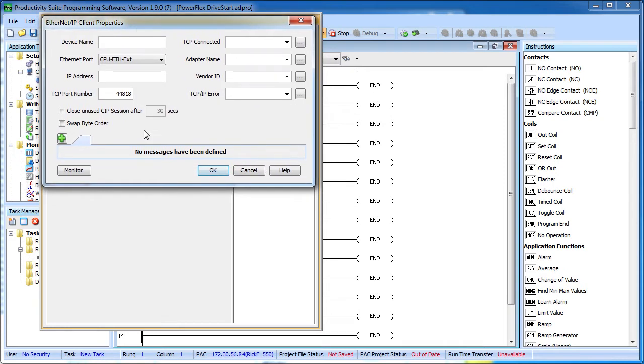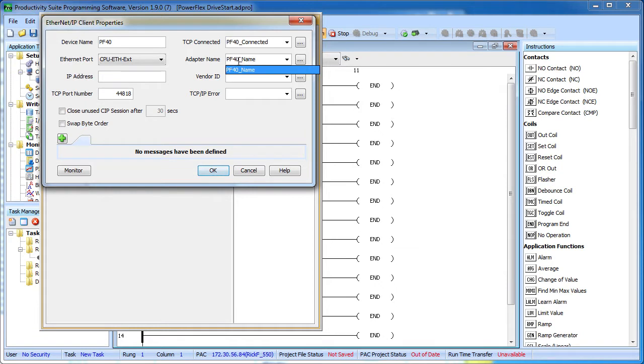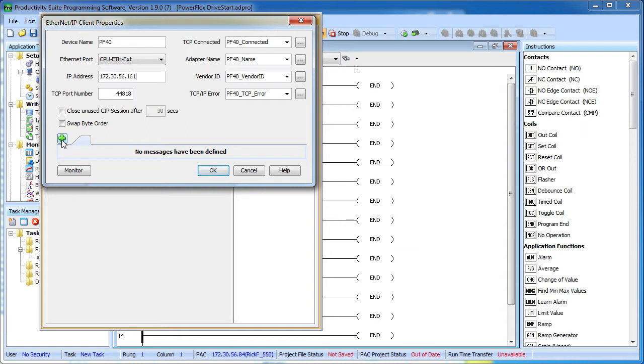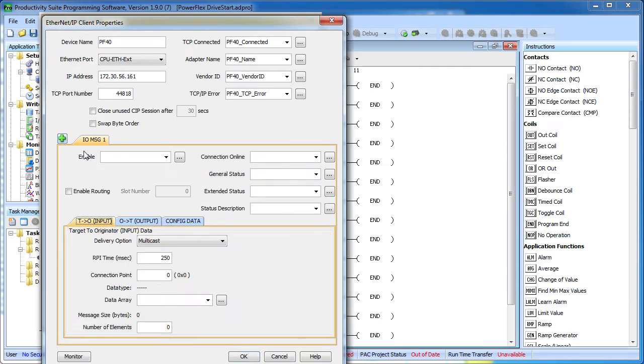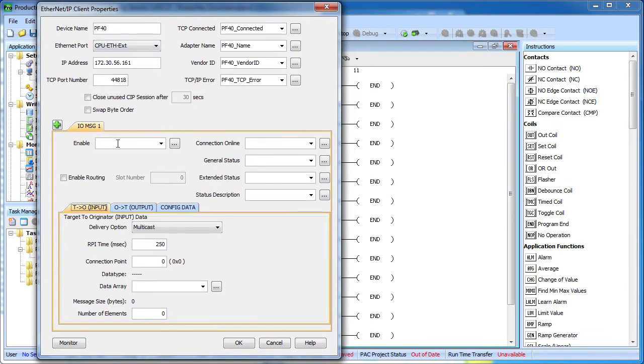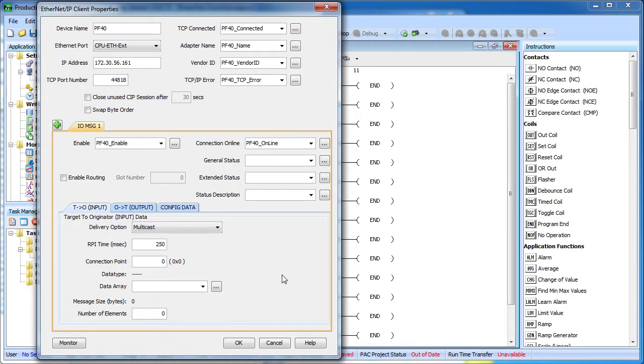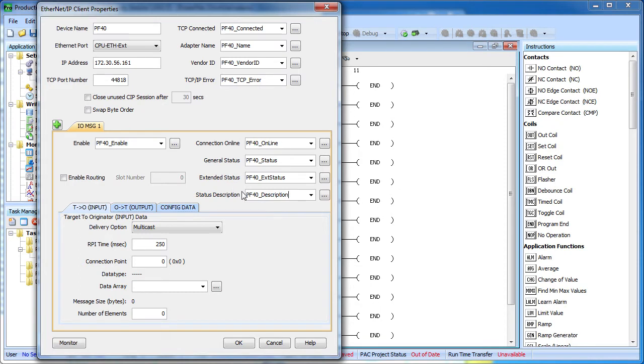Now we just fill in the blanks. Here we give it a name. Over here we create tags to collect device info and monitor the connection status. And over here we provide the IP address of the device we want to talk to, the Flex drive in this case. Down here we select the messaging protocol we want to use, in our case it's the I-O or implicit messaging, and we create a tag that we'll use to enable the data transfer. Over here we create some more tags so we can monitor the health of the connection from our ladder code. These guys are really handy as you'll see in just a moment.